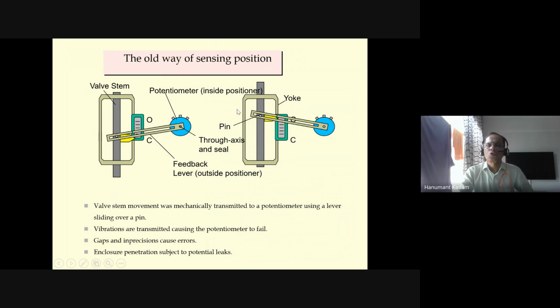So you can see this is the yoke pin here for fixing. What was happening here? Valve stem movement was mechanically transmitted to a potentiometer using a lever sliding over a pin. So vibrations are transmitted, causing the potentiometer to fail here. Gaps and imprecision cause errors. Here we have a loosened screw, the gap, and enclosure penetration subject to potential leaks. So these are the problems happening with existing positioners.